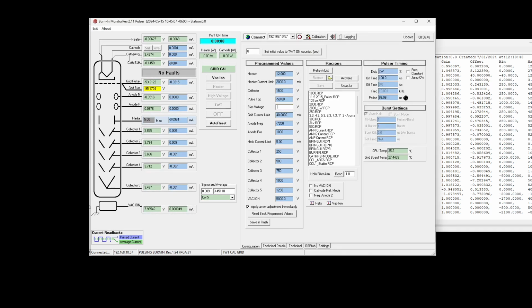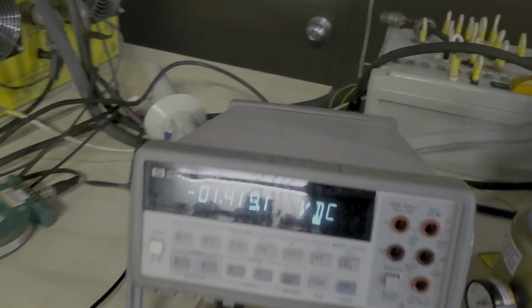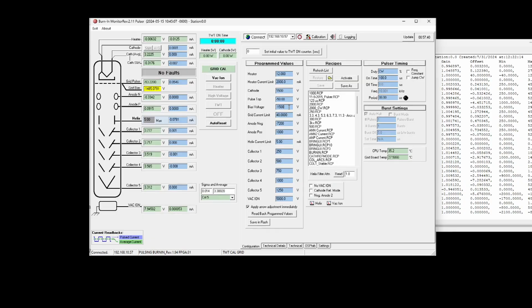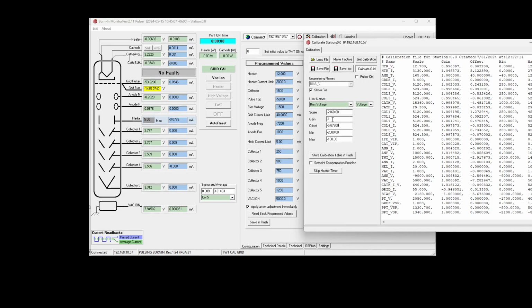Now let's bump this up to 1500. The customer can pick their target value, of course, whatever they want to run the bias at. And this would be an ideal calibration point for them. So I see 1485. Let's go see what the DMM says. 1419.0. So that's definitely too far. We're just going to adjust gain until we read 1419.0.